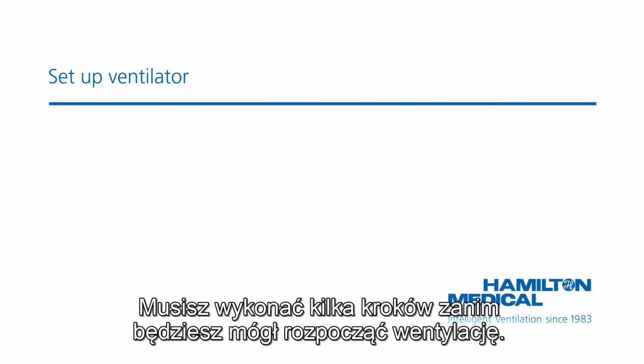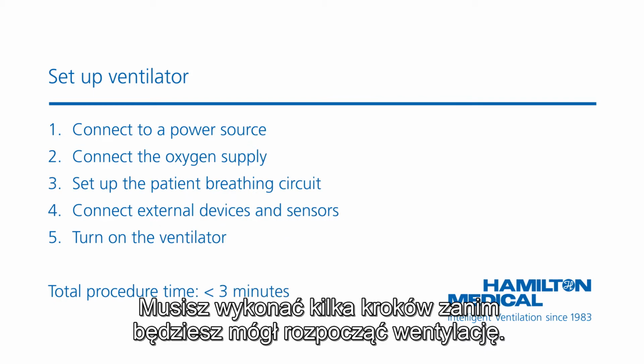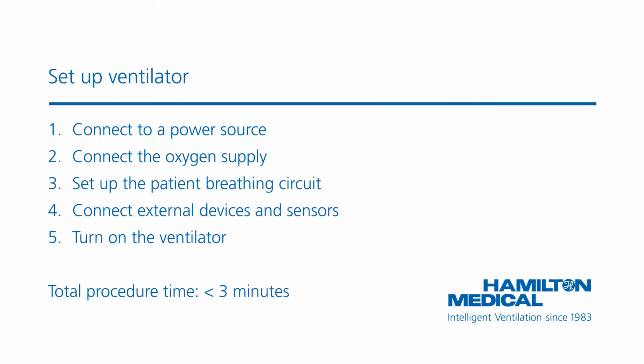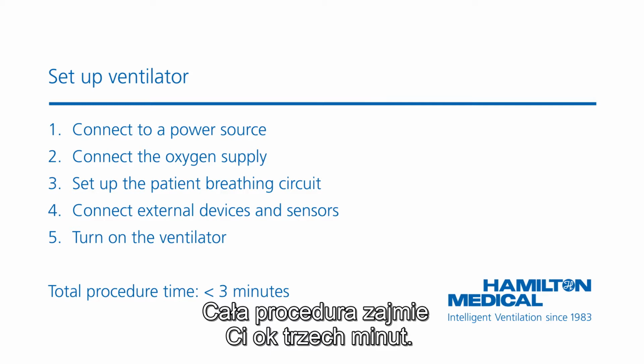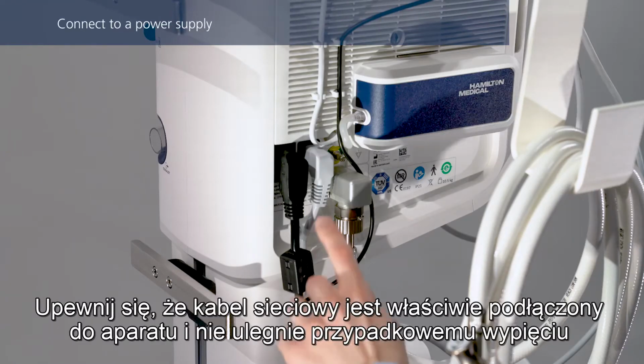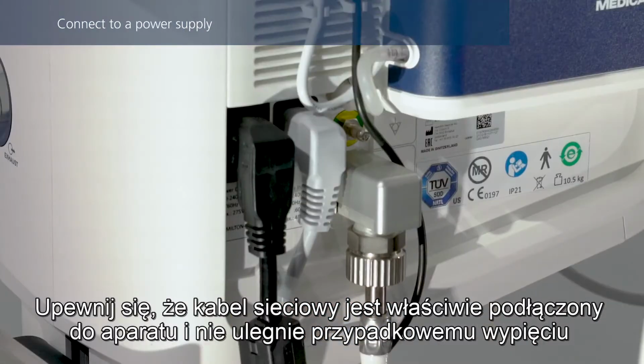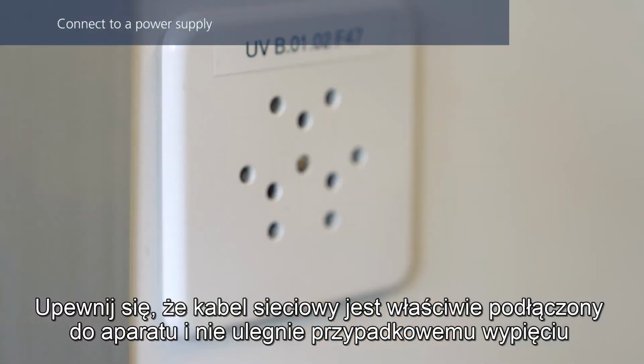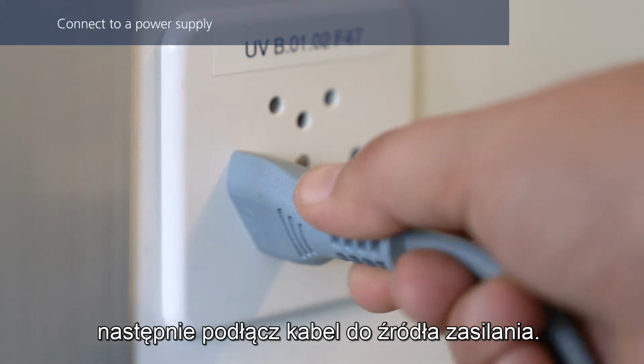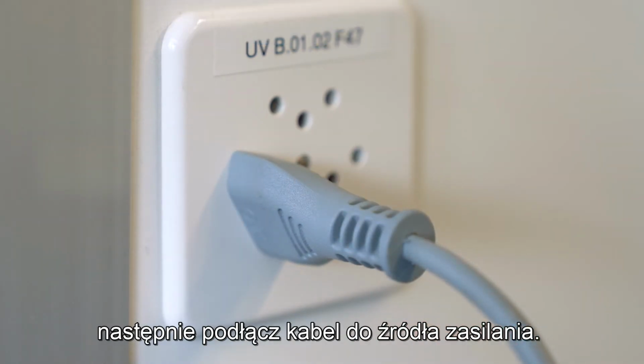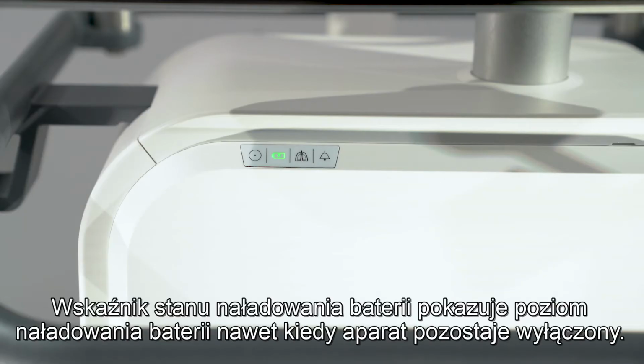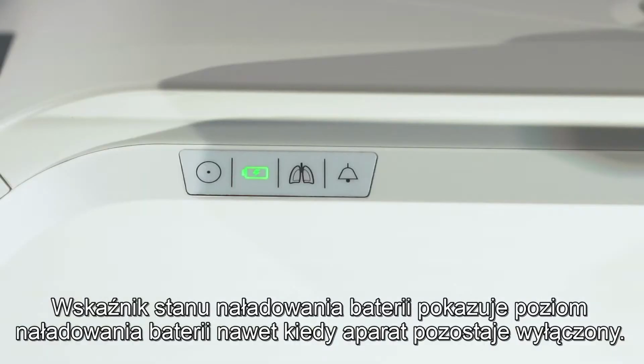There are a few steps you need to follow before starting ventilation. The whole procedure takes approximately 3 minutes. Make sure the power cable is firmly connected in the socket to prevent accidental disconnection, and then connect it to the primary power outlet.